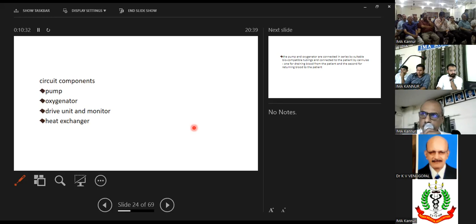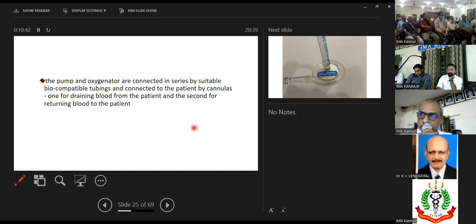The oxygenator is a system where you have a large number of micro tubules which are composed of a semi-permeable membrane, and that allows gas diffusion across the membrane. So on one side you have the gas, and on the other side you have the blood, and the flow rate determines how much oxygenation you get. The drive unit, there are several companies which make them, and for each drive unit, the pump also is specific. Now, the heat exchanger is necessary because once you take the blood out, especially in ICU where the AC is running very high, you will find that over time the patient becomes very hypothermic and loses temperature very fast. So you have to keep rewarming the blood.